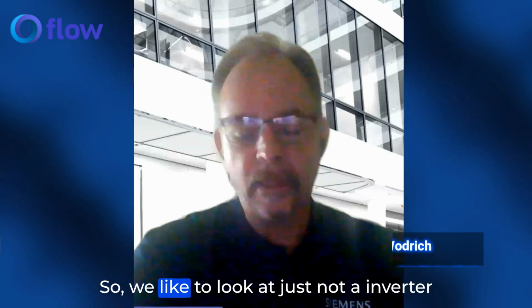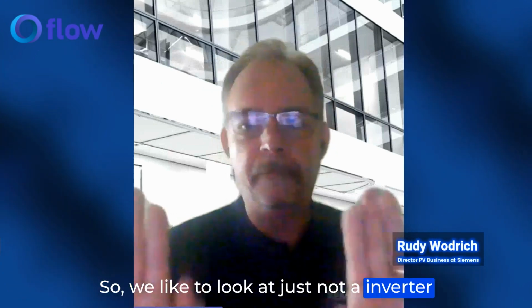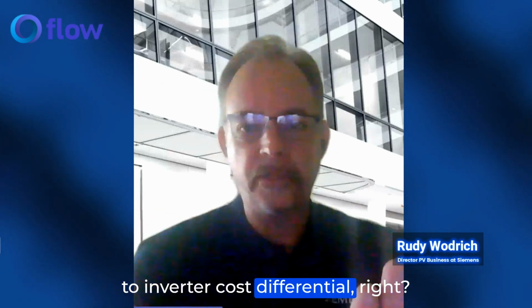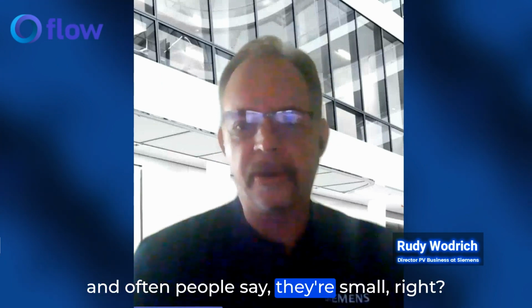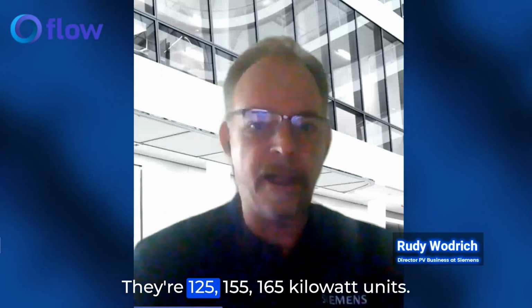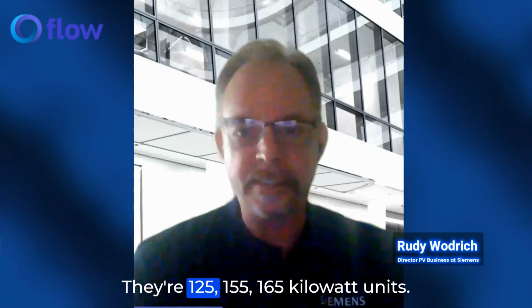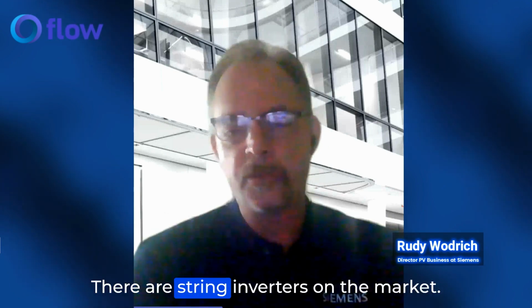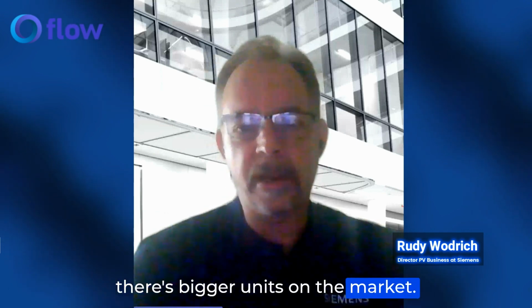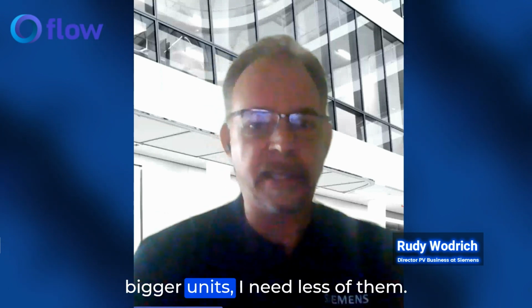We like to look beyond just an inverter-to-inverter cost differential. We have these single MPPT inverters, and often people say, well, they're kind of small, 125, 155, 165 kilowatt units. There are string inverters on the market that are 250, 255, 350, 333 kilowatts. So there are bigger units on the market, and the argument is, if I use bigger units, I need fewer of them.